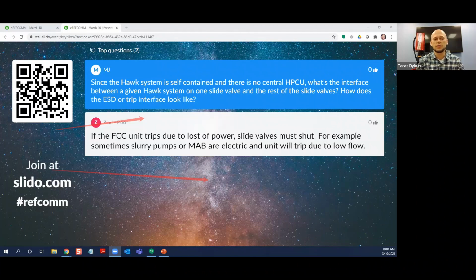Well, it's basically just receiving a 4 to 20 milliamp signal, right? You have a unit right here, actually on the back, where you just feed 4 to 20 milliamp on these cables, and then you receive a signal, and it operates exactly the same way as an HPCU. So nothing crazy, nothing particular. It can also send out Modbus signals to you if you need any alarms.